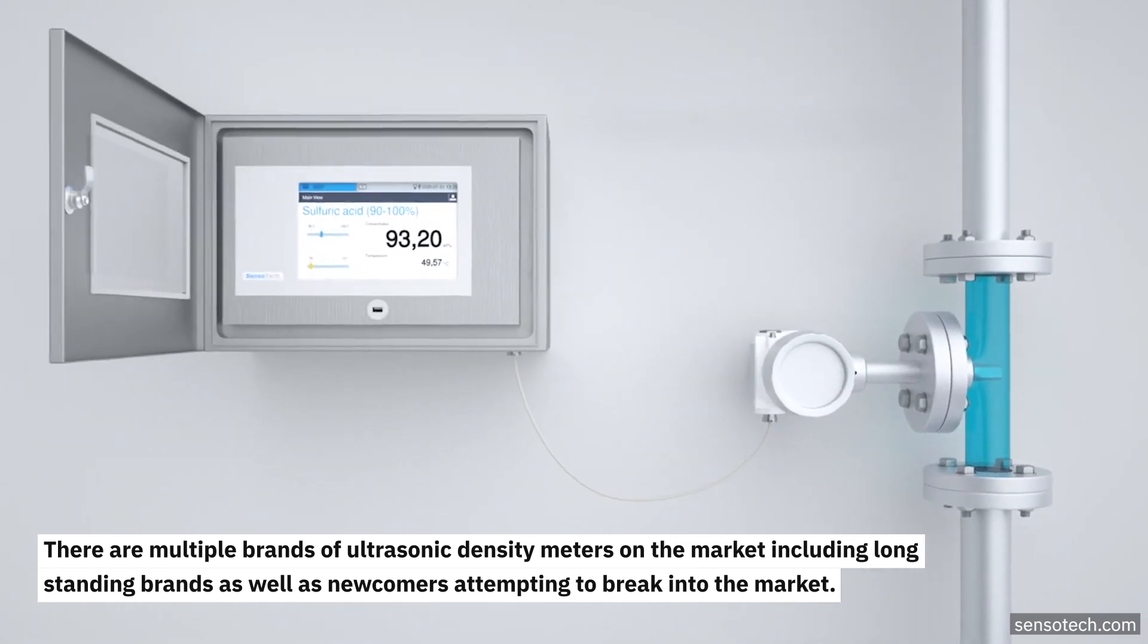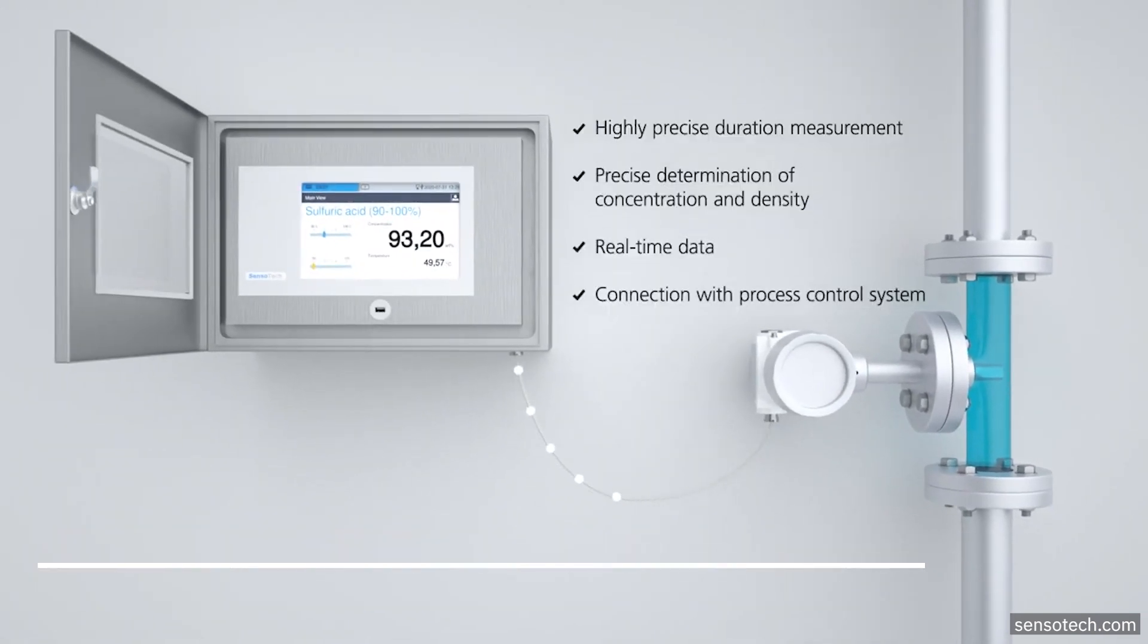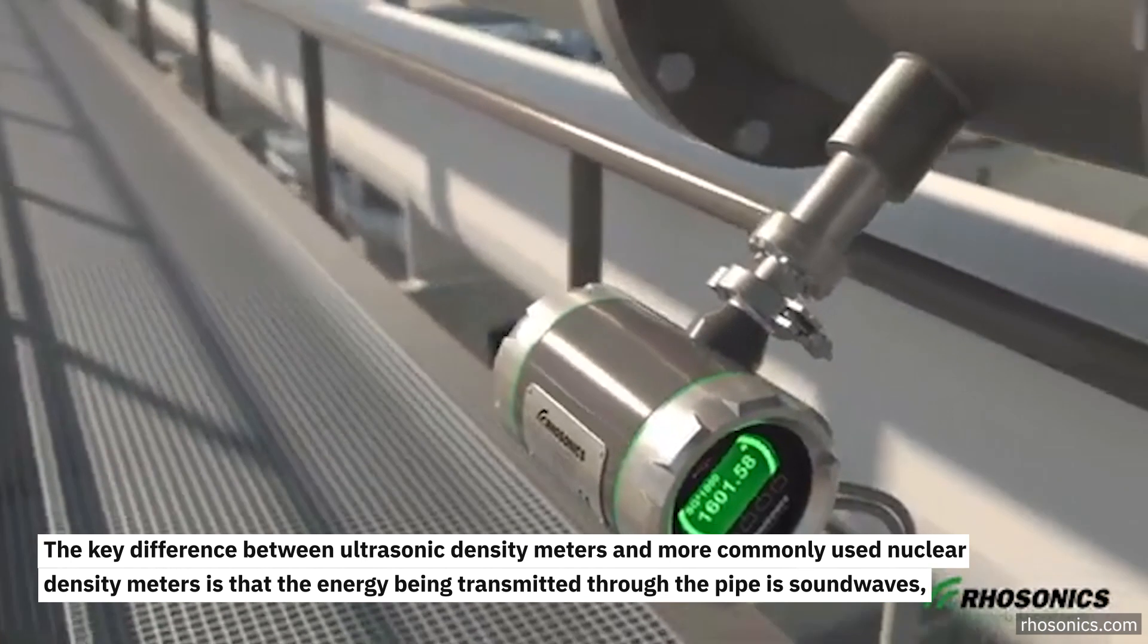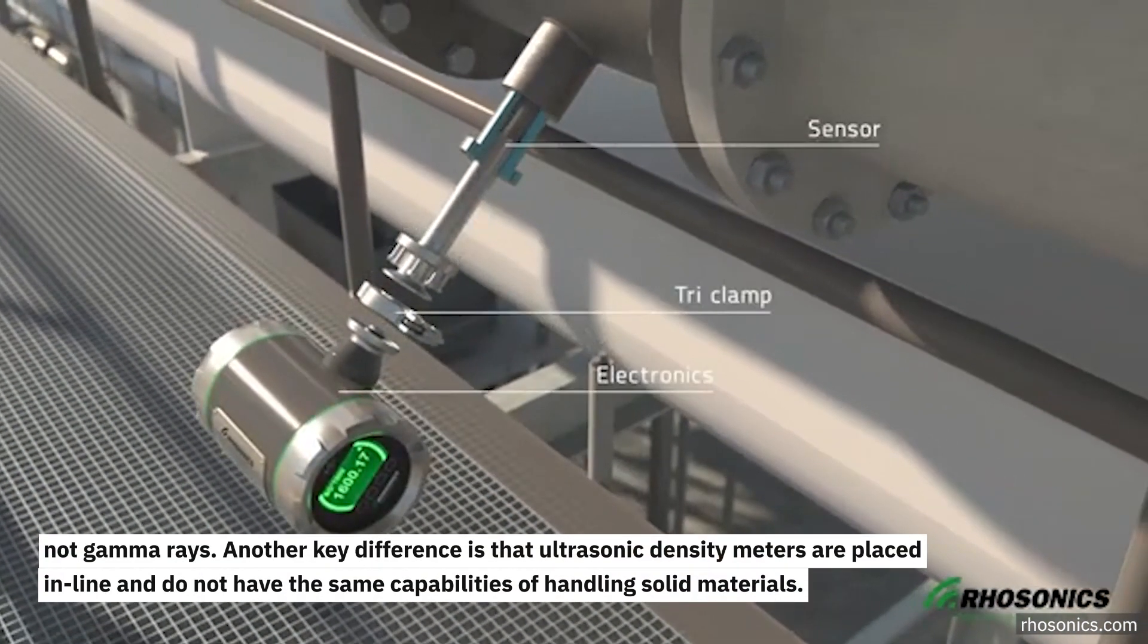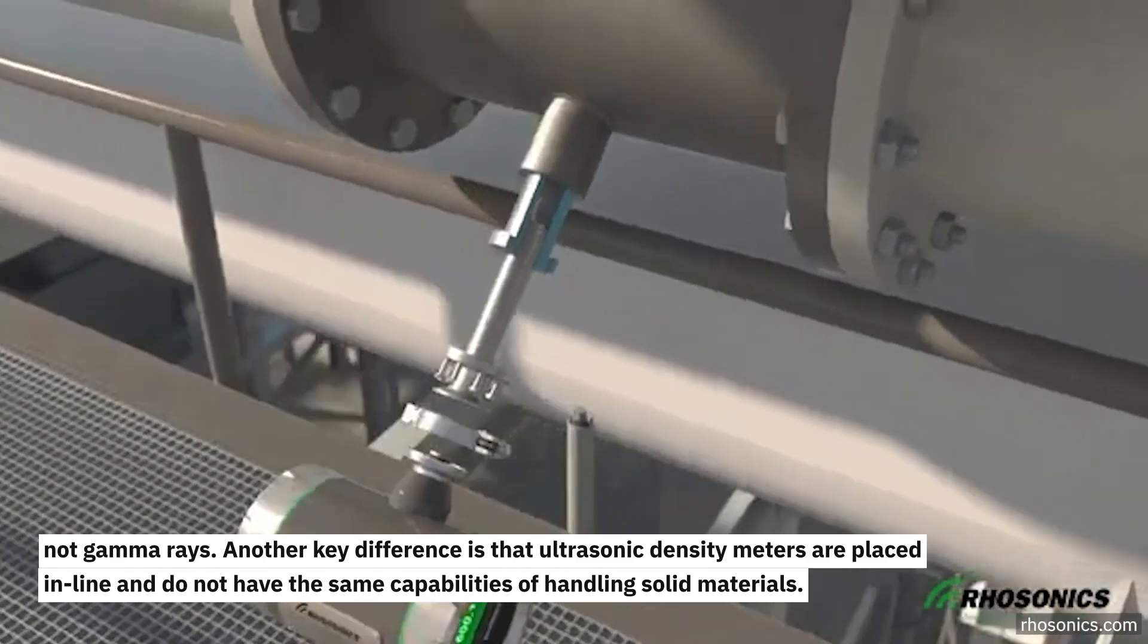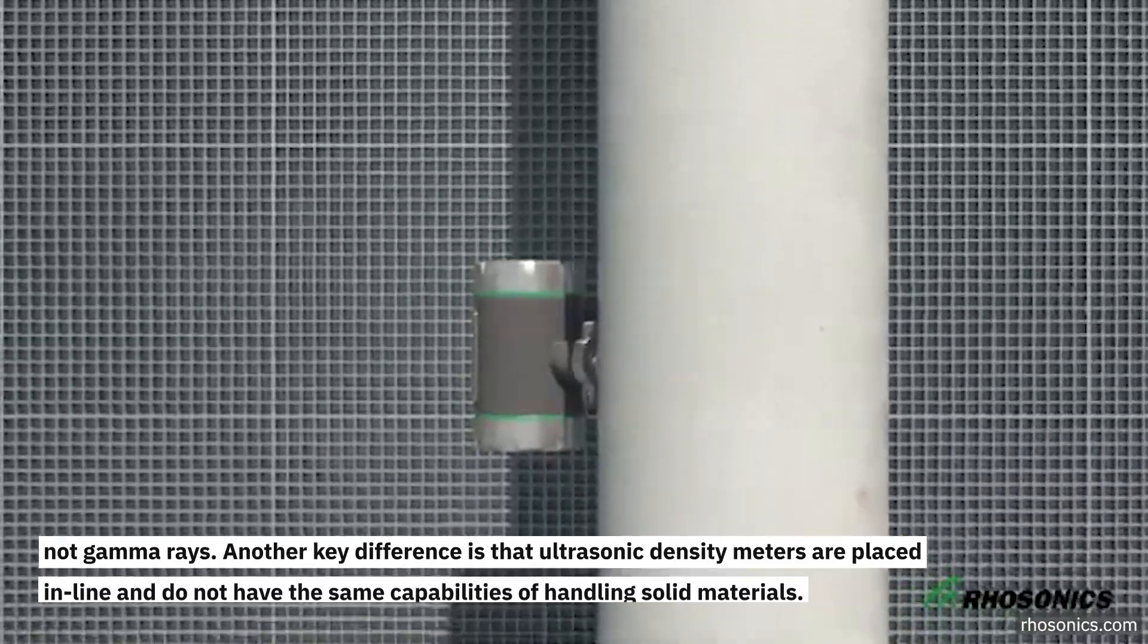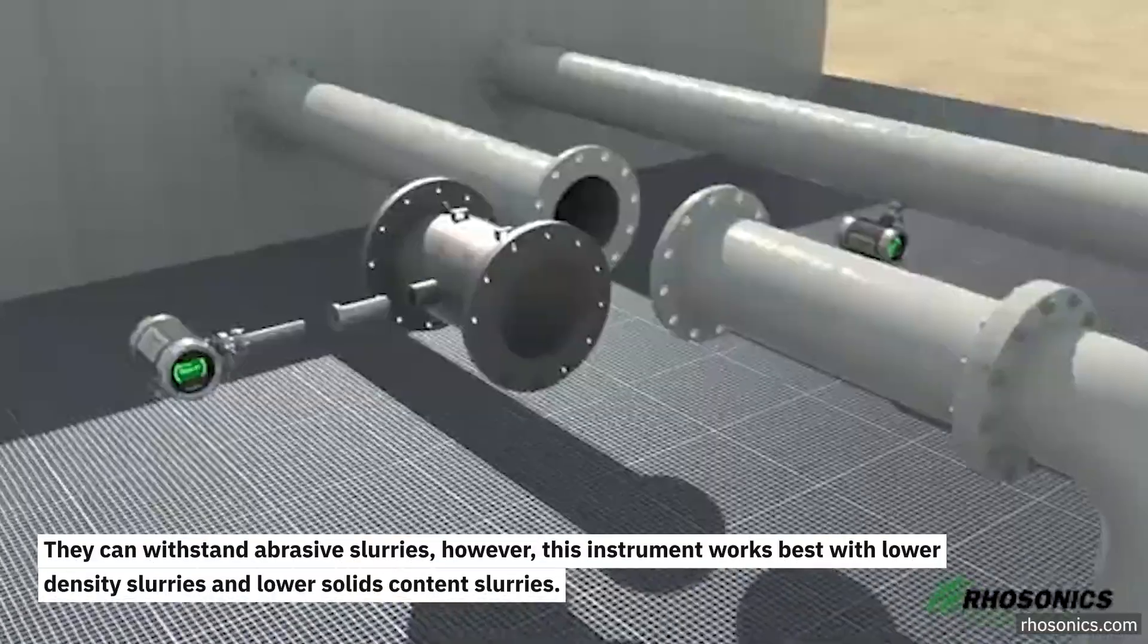The key difference between ultrasonic density meters and more commonly used nuclear density meters is that the energy being transmitted through the pipe is sound waves, not gamma rays. Another key difference is that ultrasonic density meters are placed inline and do not have the same capabilities of handling solid materials. They can withstand abrasive slurries; however, this instrument works best with lower density slurries and lower solid content slurries.